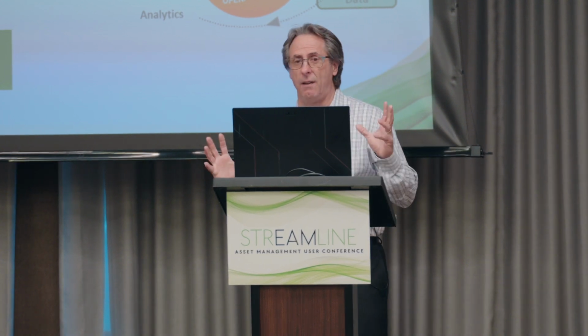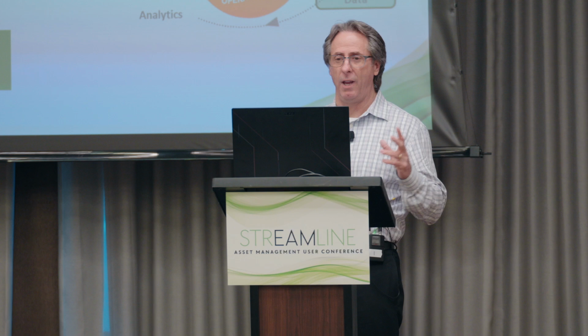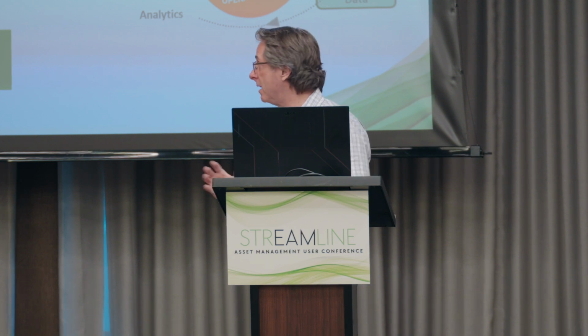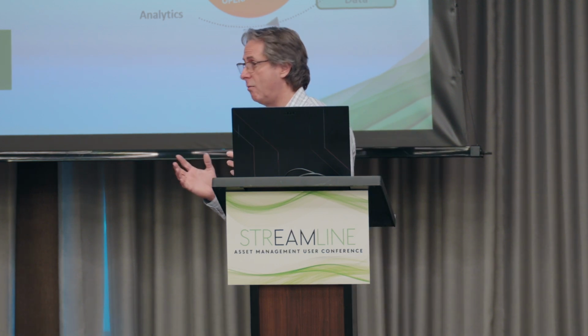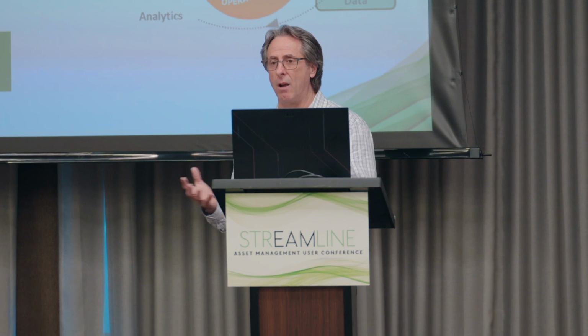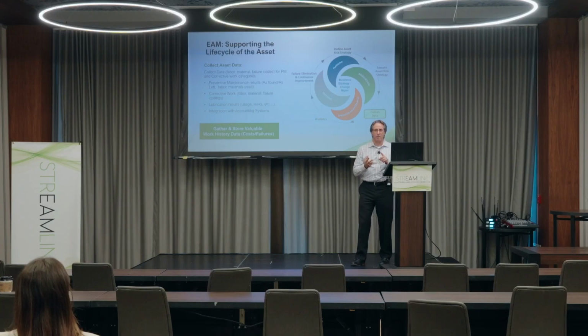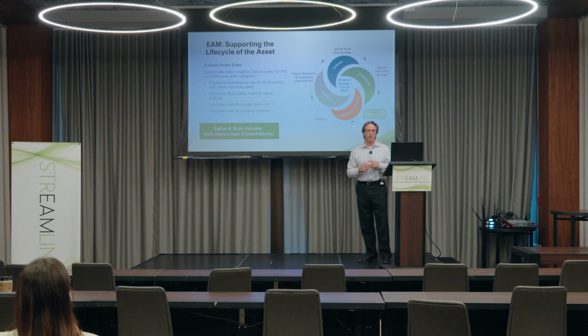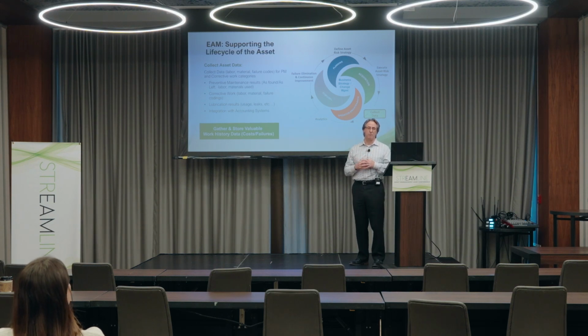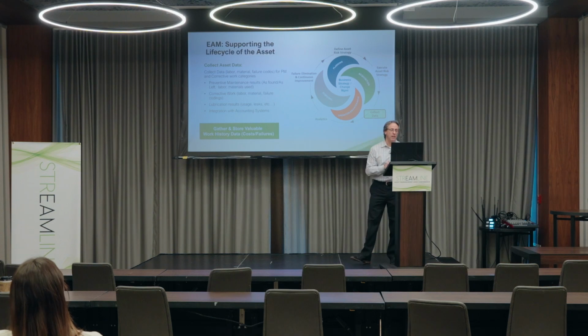So with that on the execution piece, let me move on to the next as far as data collection. There's a lot of applications out there we all work with, historians and APM solutions and production systems, but for purposes of this presentation, I'd like to focus from an EAM perspective on the work execution side. We're really gathering cost data, right? We're gathering labor, material, overhead when we go out and execute that work from a PM perspective or a corrective work. But there's a few other pieces of data that we're gathering as well. On a PM, we're gathering the as found, as left condition, so we can understand that. And as well as when we do corrective work, we're gathering problem, cause, and remedy codes when we're actually doing the work, so we can mine that data later in the process. So really a lot of critical information.